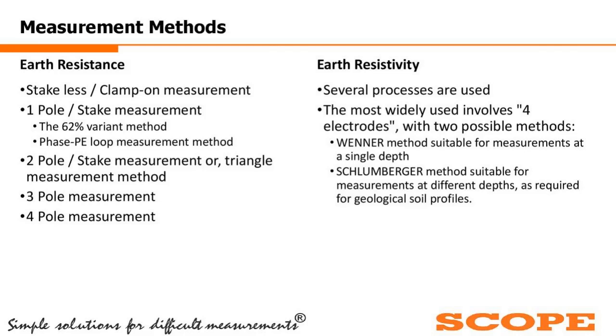And there is one more thing that might be coming into your mind: we have heard about the fall-of-potential method. What is that? The fall-of-potential method will be coming up once again in detail, as fall-of-potential is not a testing method. It is talking about the process, when we are doing the four pole measurement or three pole measurement, of how the measurement should be carried out. That is called the fall-of-potential. So it is not the measurement principle, it is a measurement method, how to do it, something like good practices. I will be coming into that also in the subsequent slides.